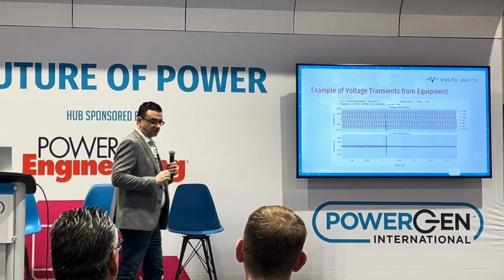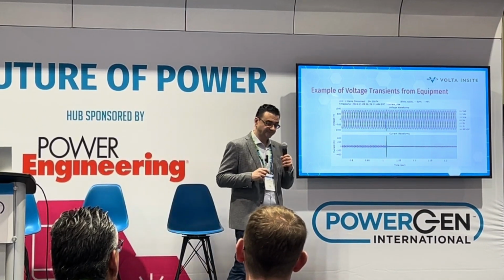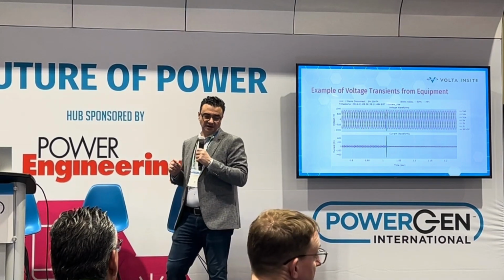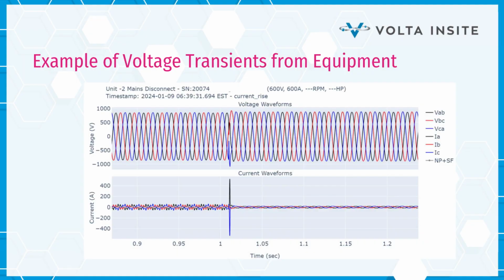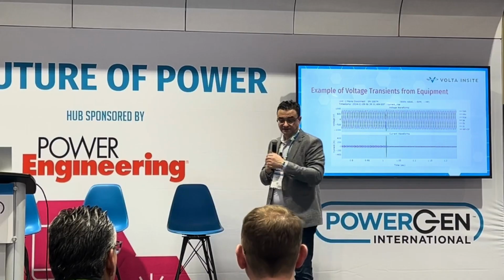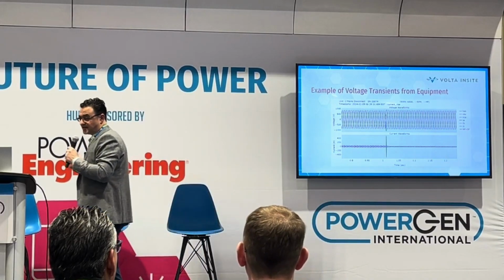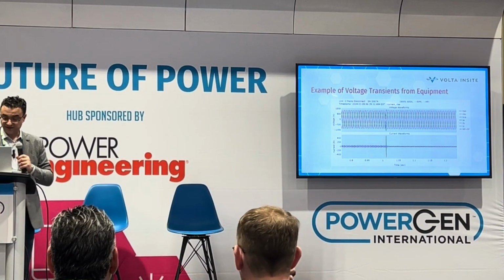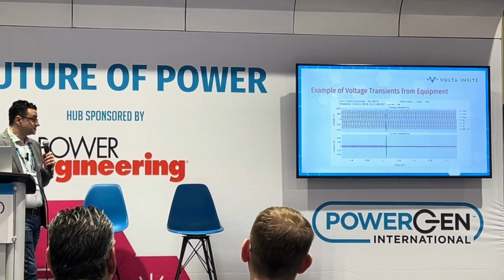Further, this is an example of a voltage transient because of equipment. You'll notice that on the left-hand side of the graph, on the current side, we have a lot of switch mode power supplies happening, and I believe this is from some lighting equipment ultimately. And as we progress, there's a transient that happens because this lighting equipment turns off, and we get a huge spike of current, which also affects the voltage. Now, that may or may not be an issue, but if that starts happening continuously and repetitively at a high frequency, you could damage equipment.